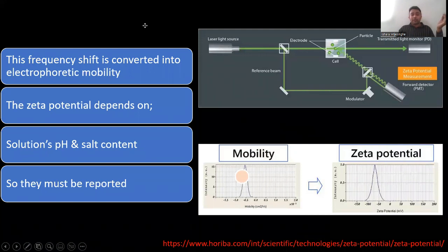In this instrument, you can see a laser light is there. We pass that laser light and divide it into two beams to find the reference, to find out whether there are noises. And we can tare the instrument, meaning calibration. We can calibrate the instrument, removing all the noises. Now the instrument is ready to measure.